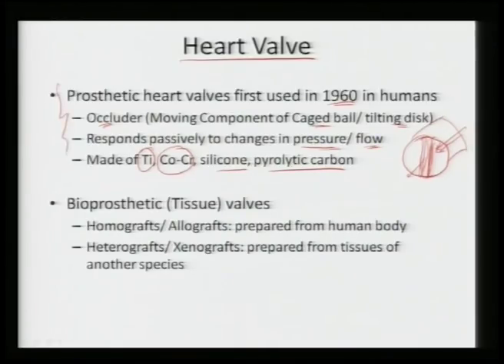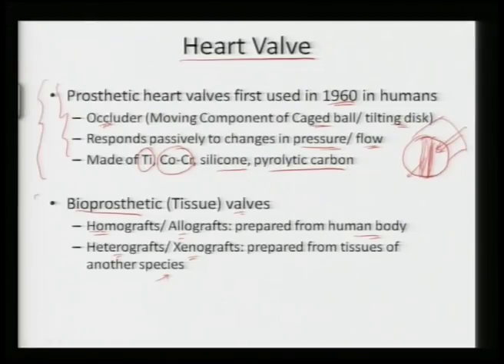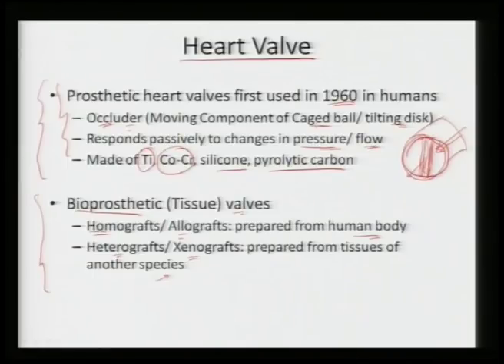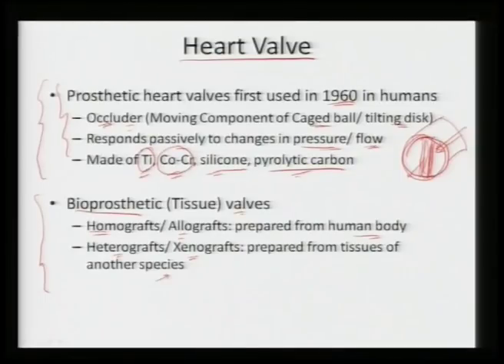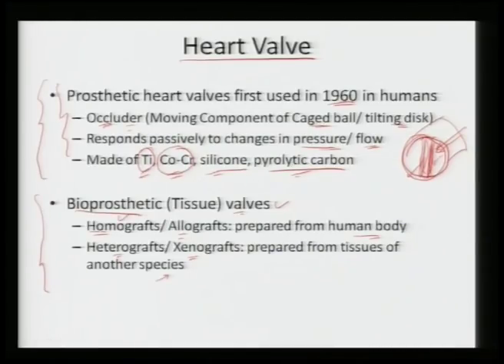Heart valves can also be bio-prosthetic or tissue valves, which are more natural. These can be prepared from homografts or allografts from the human body, or hetero-grafts or xenografts prepared from tissues of another species. Synthetic valves require an occluder — a moving disc component — made of titanium, cobalt-chromium, silicone, or pyrolytic carbon. Bio-prosthetic valves can be either allografts or xenografts depending on the source tissue.